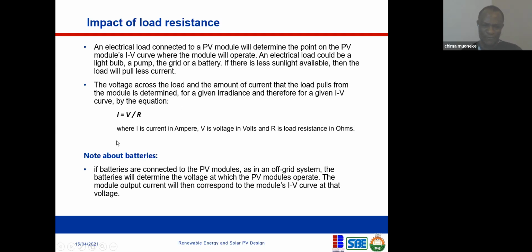A note on batteries: if batteries are connected to the PV modules, as in an off-grid system, the battery will determine the voltage at which the PV modules operate. The module output current will then correspond to the module's IV curve at that point, at that voltage.